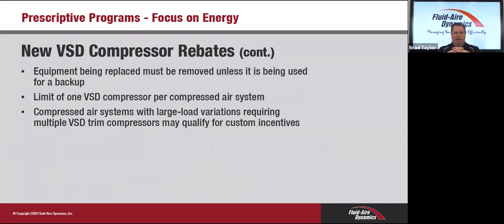And then just to continue on, the equipment being replaced must be removed unless it's used for backup. Again, we don't want to be investing incentive dollars in a project only to have the lesser efficient compressor running as primary. So there's a little bit of setup in the controls so that we have the more efficient compressor be the primary. We limit 1 VFD per system, and compressor system with large load variations requiring multiple VFD trim compressors may qualify for a custom incentive. Laura, is there anything you can add to that?